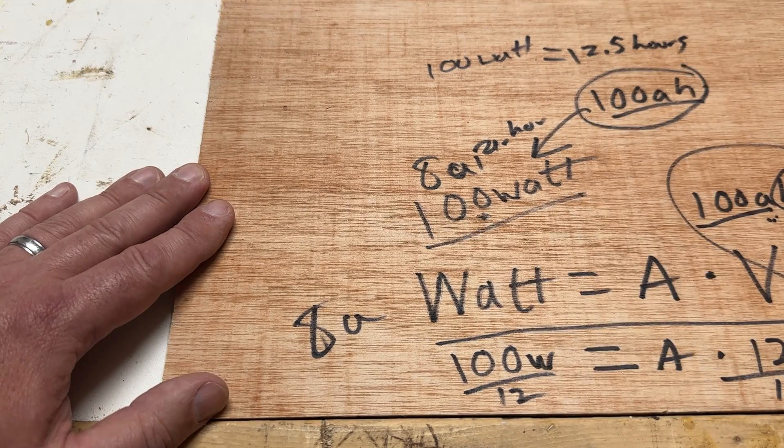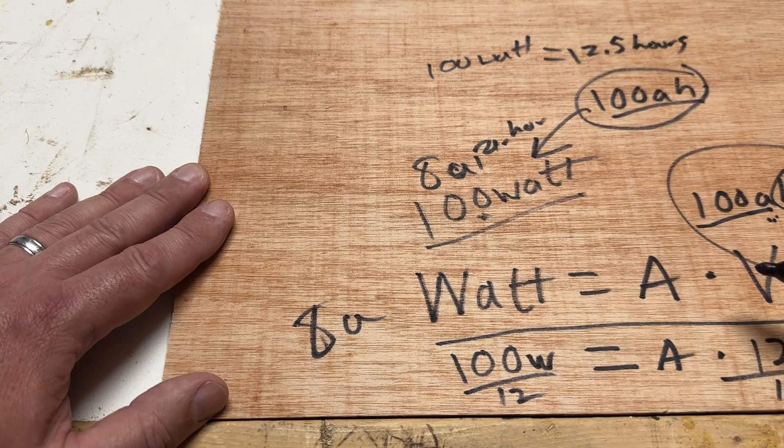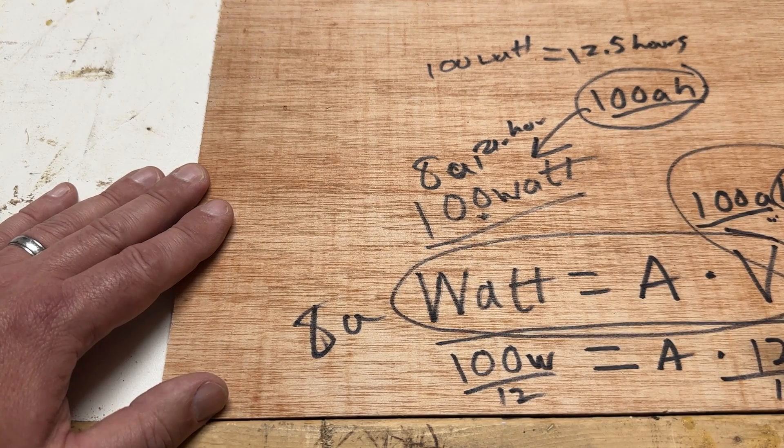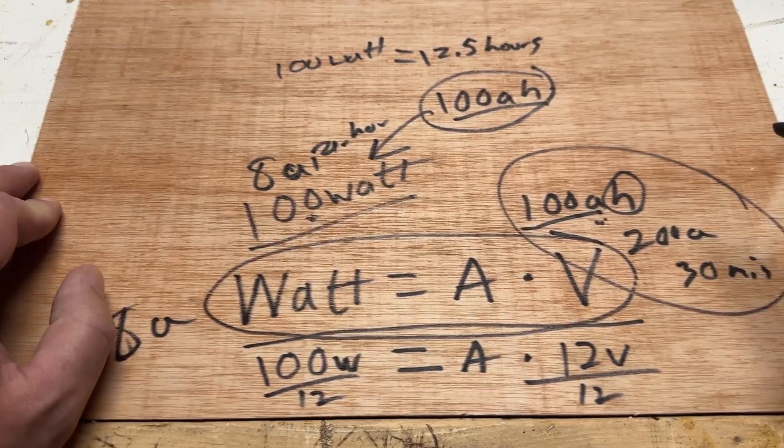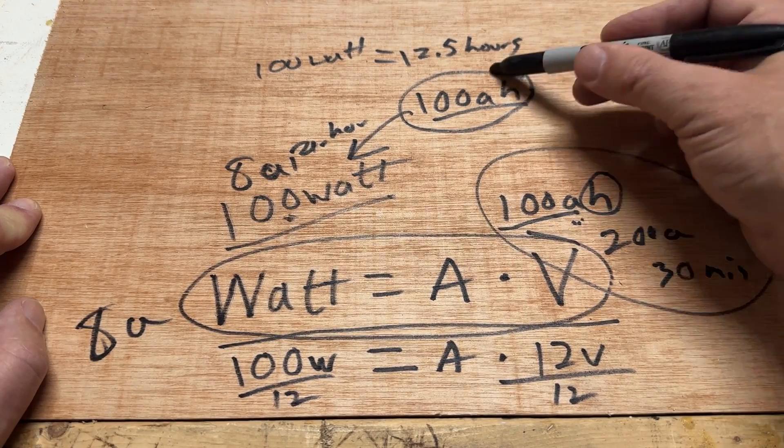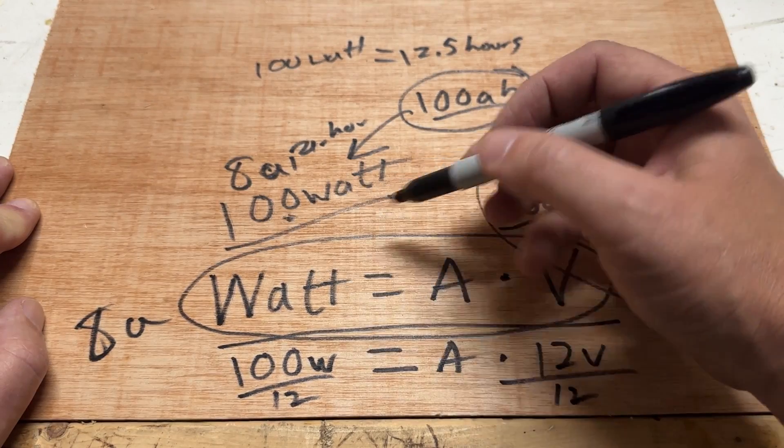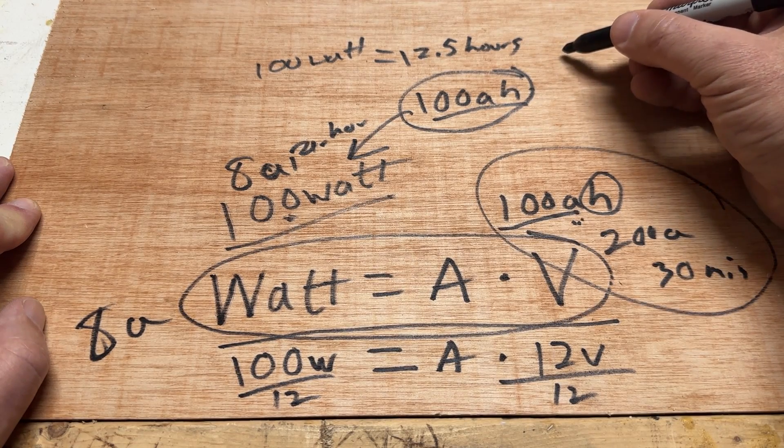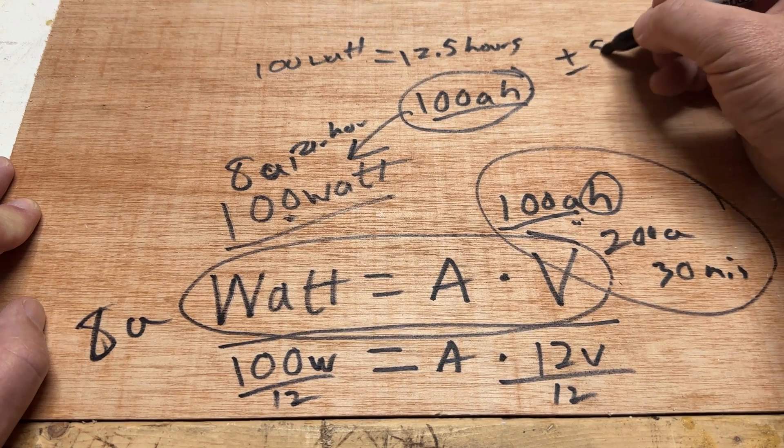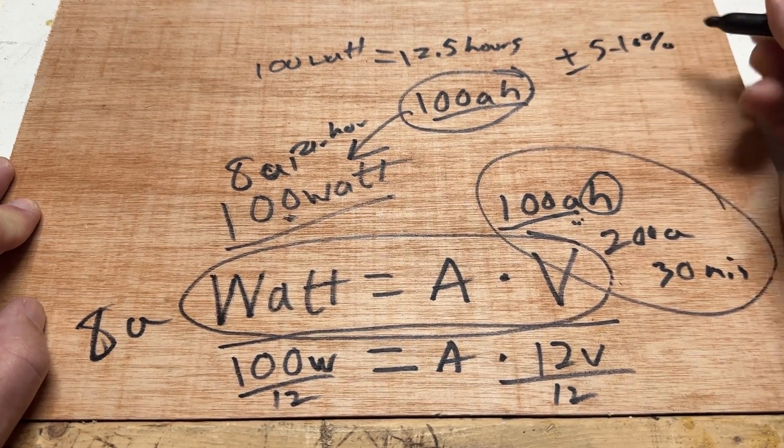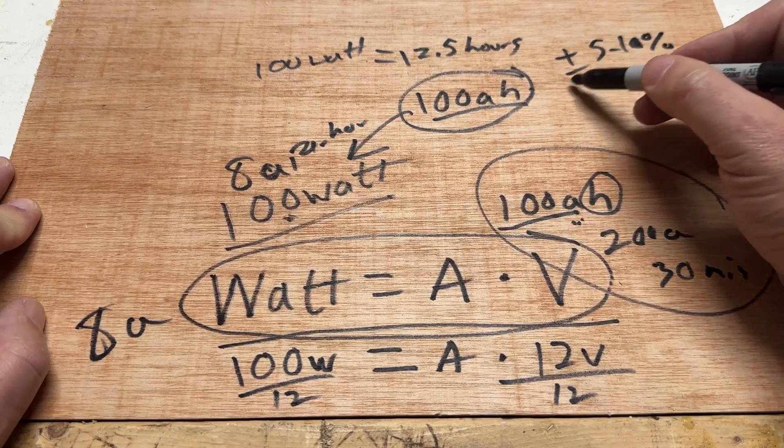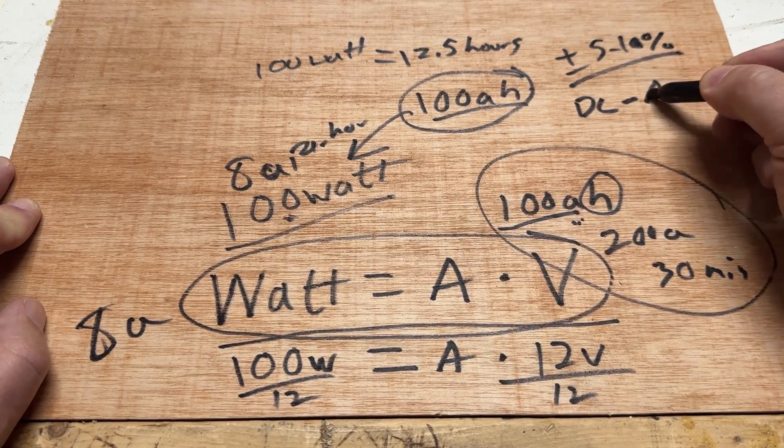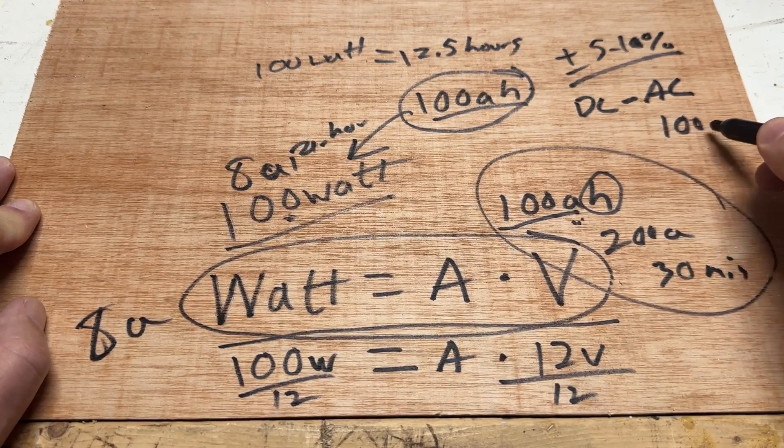These are all very rough estimates, okay? But this is how we figure that out. This is the only formula that you need in order to solve all those equations and problems, and then a few basic bits of math. Now there are a few things you want to consider here. If you're running things through an inverter connected to your battery, then there's going to be a loss there. You're going to lose, let's say plus or minus 5% to 10% of your overall capacity. There's some efficiency loss there when you're running things through an inverter.